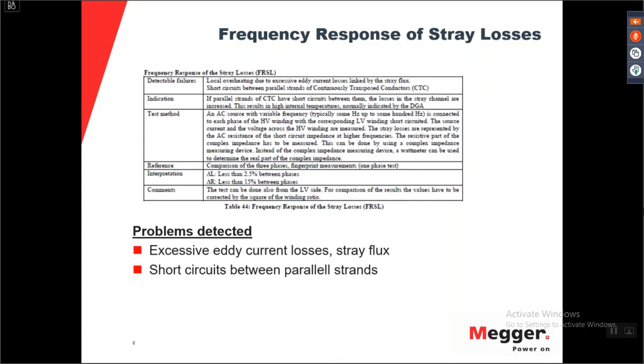The test method is an AC source with variable frequency in the range of some hertz up to 100 hertz. And you connect it to each phase of the high voltage winding with the secondary side short-circuited. Then you measure the voltage and the current that you send in. This is actually the exact same thing as the short-circuit impedance test, but instead of doing it at the rated frequency, you apply this at a frequency range.